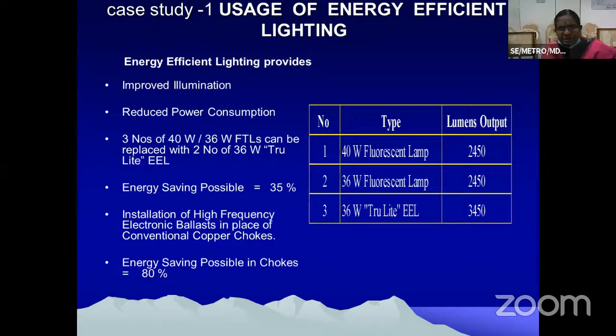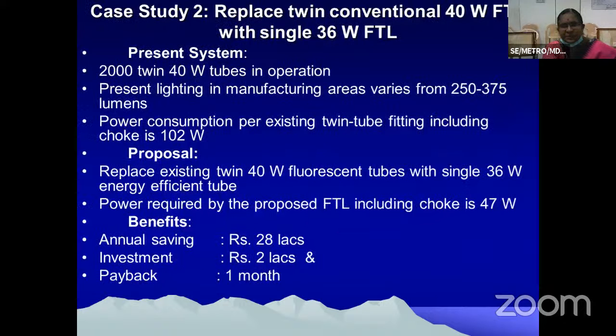Installation of high frequency electronic ballast in place of conventional copper chokes. Energy saving possible in chokes is around 80%. So this is a typical case study where they have practically implemented and given a proposal. 2000 twin 40 watts tubes in operation in an industry. Present lighting in manufacturing areas varies from 250 to 375 lumens. Power consumption per existing twin tube fitting, including choke, is 102 watts. So they had a proposal to replace the existing 40 watts tube lights with a single 36 watts energy efficient tube.